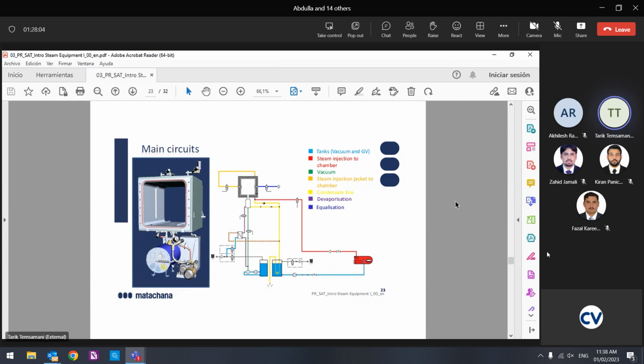Okay, the jacket has steam and has pressure inside. Then we start our cycle with the vacuum, and when we need steam injection to the chamber, we get it from the jacket, not from the steam generator. The jacket, we open this valve and we get the steam. Why do we do that? First, if we put steam directly to the chamber, with the difference of temperature, we can get a lot of condensation. Second, we always keep the temperature of the chamber hot.